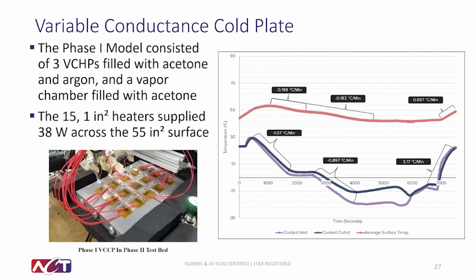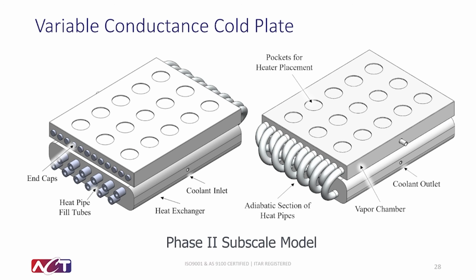During the ongoing Phase 2 program, ACT is currently in the process of fabricating another subscale prototype. This time we're using ammonia as the working fluid, as it is preferable for space applications. This model was designed using the same analytical model as described previously. The CAD image on screen shows what this model would look like if we chose to additively manufacture the plate in one go, with the adiabatic section of the heat pipes wrapping around to form a compact cold plate.